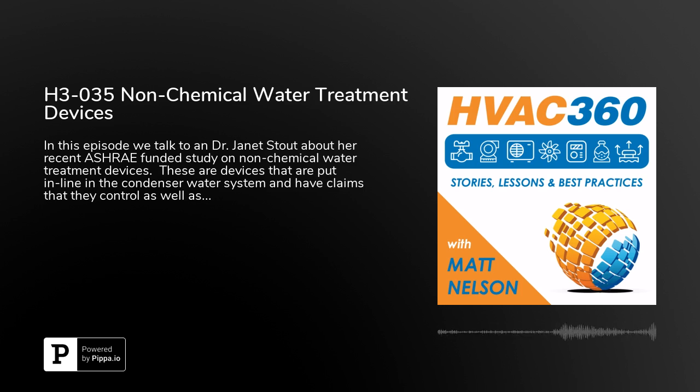Yes, and probably some of your listeners have had experience in the field with this kind of thing. What it shows is that even though we know that chlorine is an effective biocide, and this is what was being used at about 10 parts per million in between each run, there's a limit to the efficacy of chlorination to clean a complex network of pieces and parts. This is true in cooling towers and in water distribution systems. Chlorine is quickly inactivated by organic material. The efficacy of any disinfectant is limited by the old contact concentration versus time. You have to get that disinfectant to every part of whatever it is you're trying to disinfect.